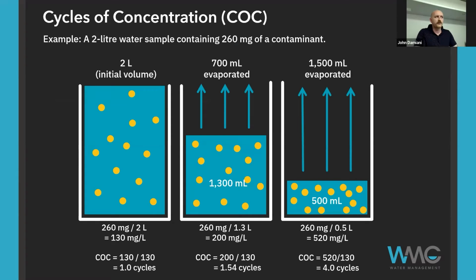Okay, so here's just a quick example. If we had 2 liters of initial volume of water, just a 2-liter bottle of water that has some amount of a contaminant in it, let's say this is the total dissolved solids, and say this could be just 260 milligrams of a single contaminant like calcium. Underneath that you can see if we have 260 milligrams of our contaminant in 2 liters, that's 130 milligrams per liter. We're dealing with water, so milligrams per liter is the same as parts per million for the purpose of this. So our cycles of concentration is very simple. We're still at our starting sample, so we're just at 1 cycle. The water we're looking at is 130, and our starting sample is the same sample. So 130 divided by 130, that's 1 cycle.